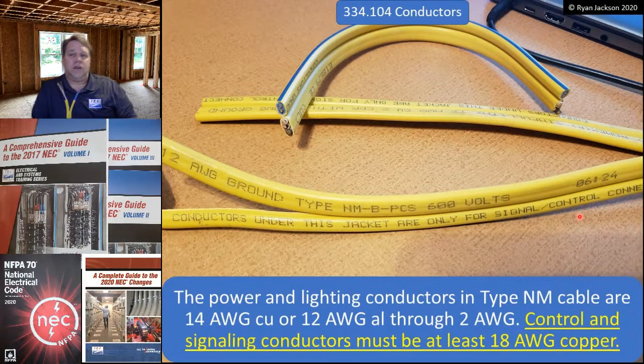Control and signaling conductors must be at least 18 gauge copper. So here I've got my 12 gauge wires, the two insulated conductors and the, is this bare? No, it's covered. Go to Article 100 and see what the definition of conductor, covered is. And then I've got my signaling circuit here, two 18 gauge conductors that are purple and gray, which we would normally use for like 0 to 10 volt dimming.